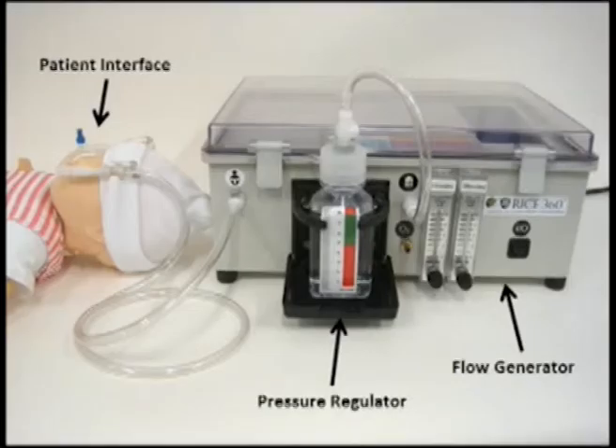With clinicians from the United States and Malawi, we tasked a team of engineering students with designing a bubble CPAP device for the developing world. In a year-long capstone design course, this team of students engineered a $160 device that delivered the same therapeutic flow and pressure as the systems routinely used in the developed world.